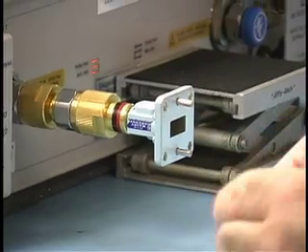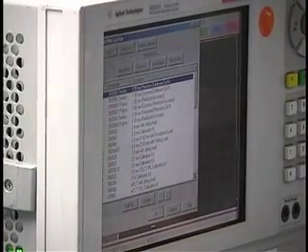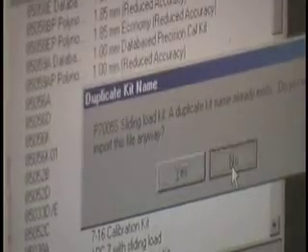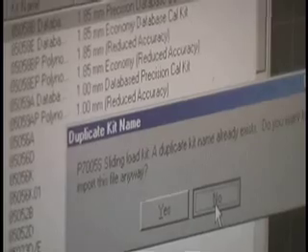We begin the cal by loading in the cal coefficients from the media. We go to the calibration pull-down menu, select Advanced Modify Cal Kit, Import Kit, and in the pull-down menu we'll go to My Computer, Removable Disk, and select the P70055 software from the drive. Since I've already loaded the software from before, we're going to say no when it asks if I want to import it again.